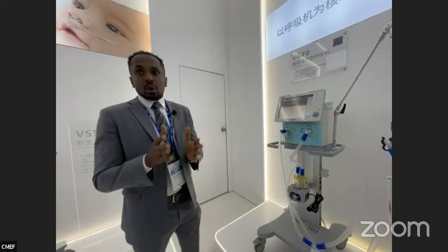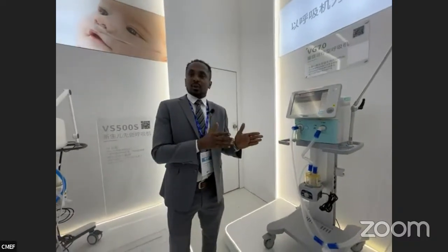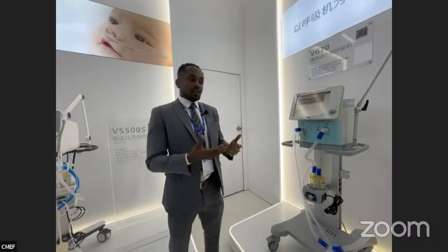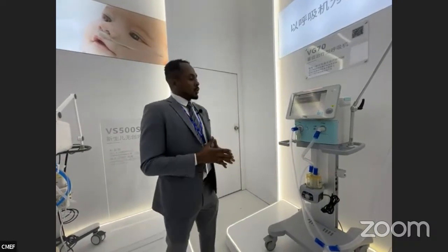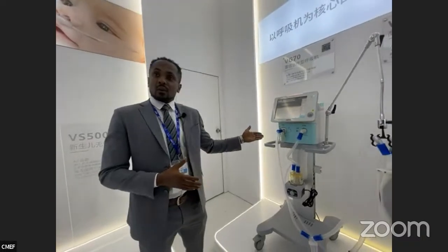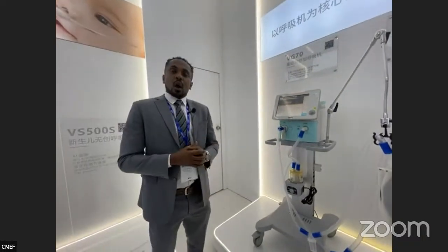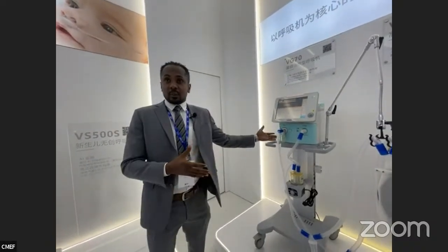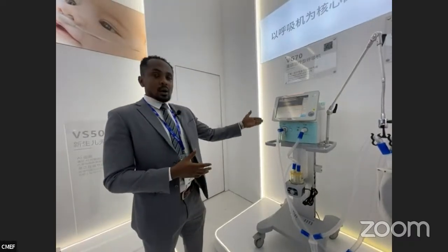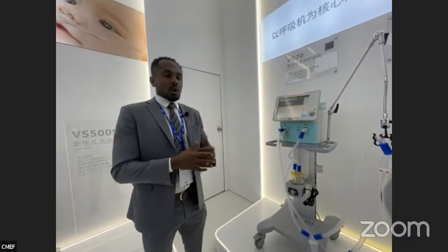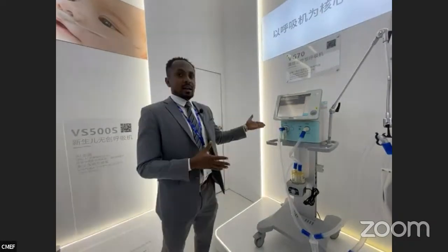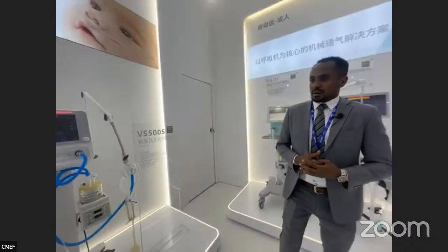Then let's talk about one of the most important features that we have on this ventilator, which is our expiration valve. Our expiration valve is made of magnesium aluminum alloy, and the whole module can be sterilized because it's a detachable expiration valve. So we can just unlock the valve and sterilize it. The whole module can be sterilized. Also, the expiration valve is heated inside, which in this way we can avoid any condensation.